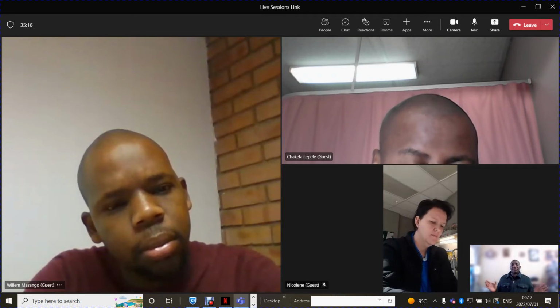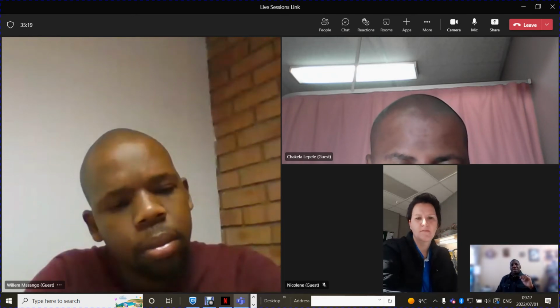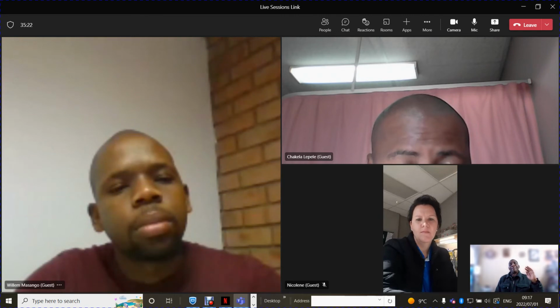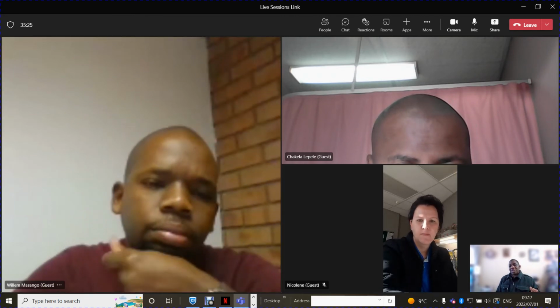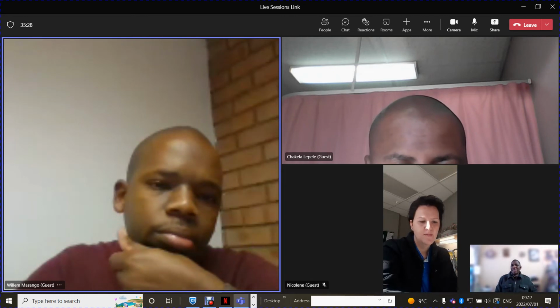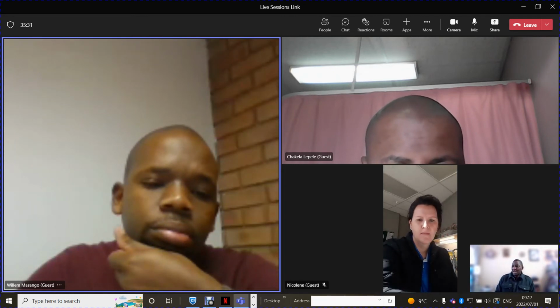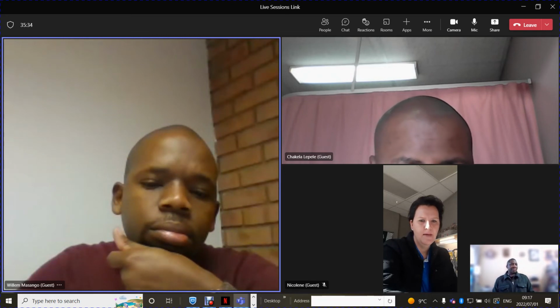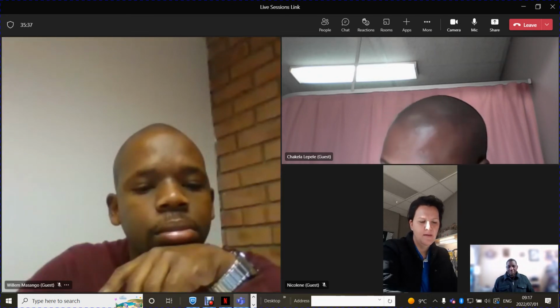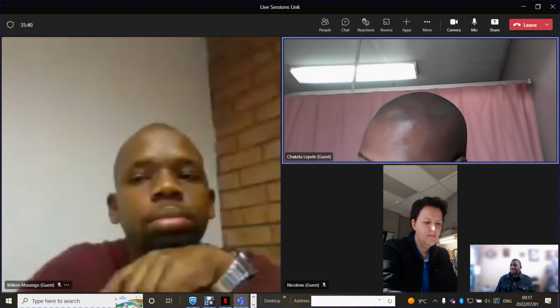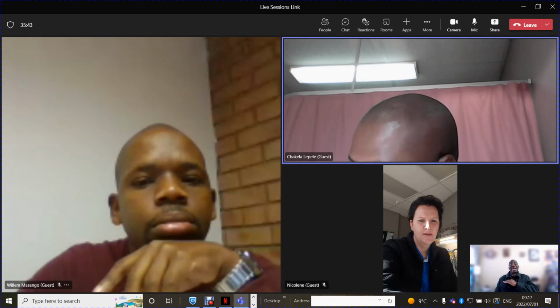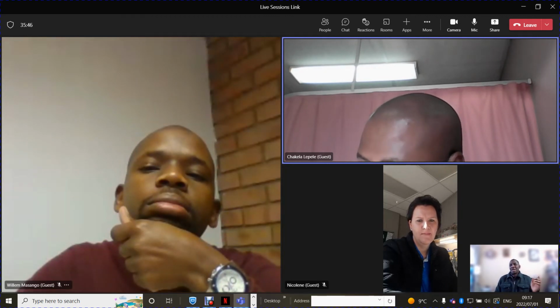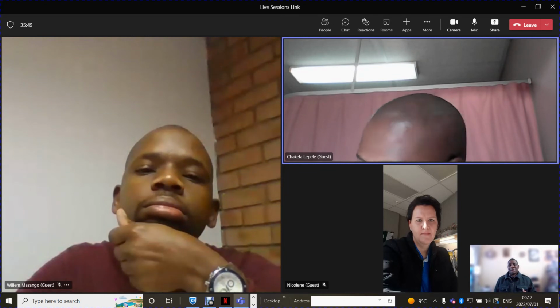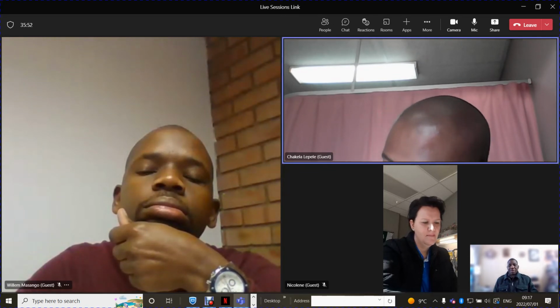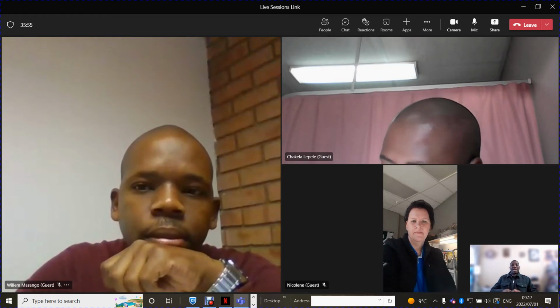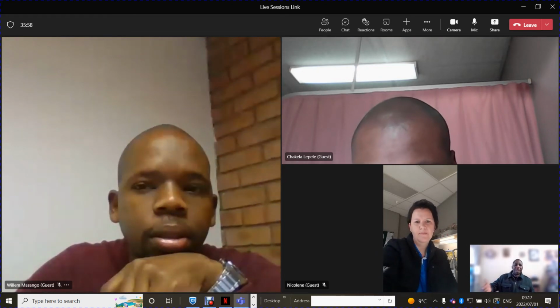When you do electrical safety testing, the allowable limit for macro shock is 20 milliamps. And for micro shock, I'll have to check the exact figures, but I think it's around 10 microamps—it must not exceed that. Otherwise, it can create problems for the heart. But I'll check and double check and confirm.